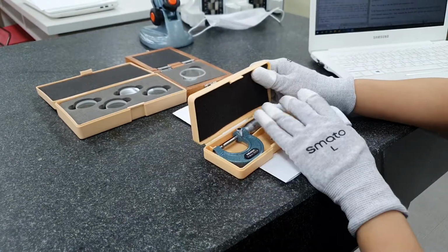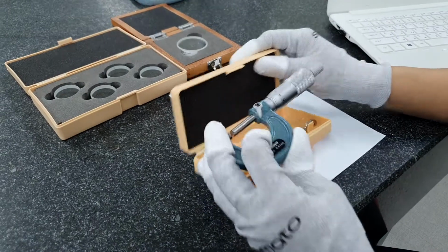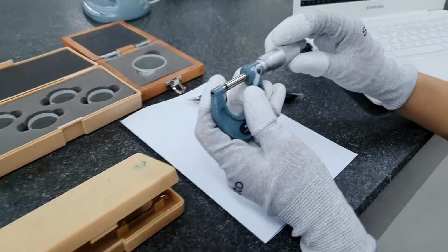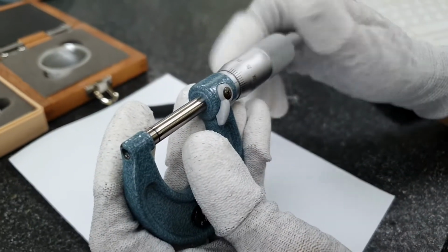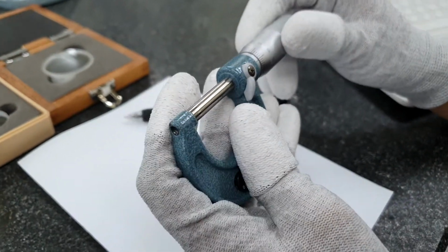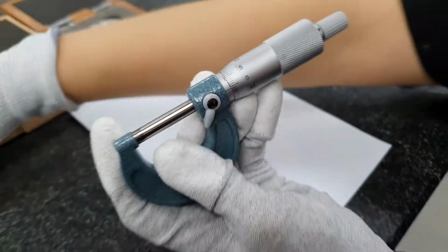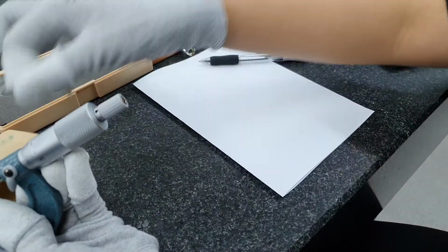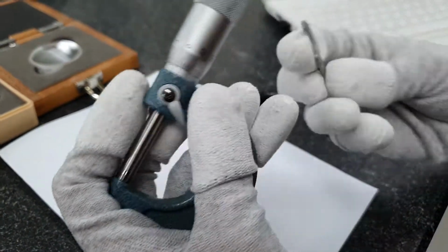At first, I will talk about the zero adjustment, which is run when the sleeve and thimble are not in a straight line of the zero scale. Firstly, fix the spindle by clamp and spin the sleeve by key spanner to make the straight line. This is not a straight line. So I will show you how to make it a straight line with the zero point.